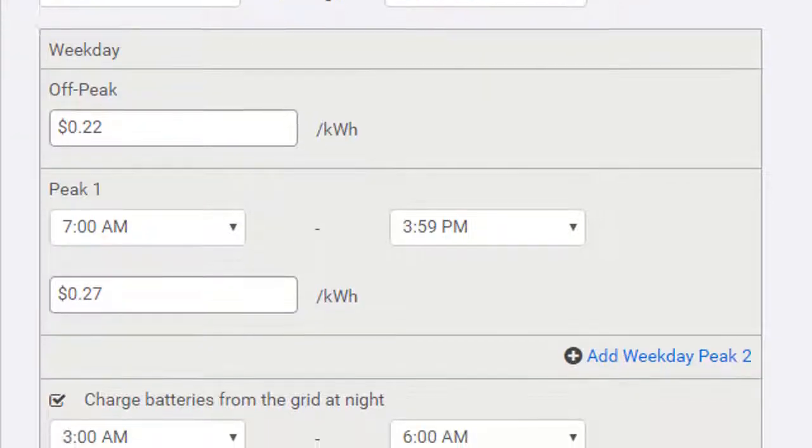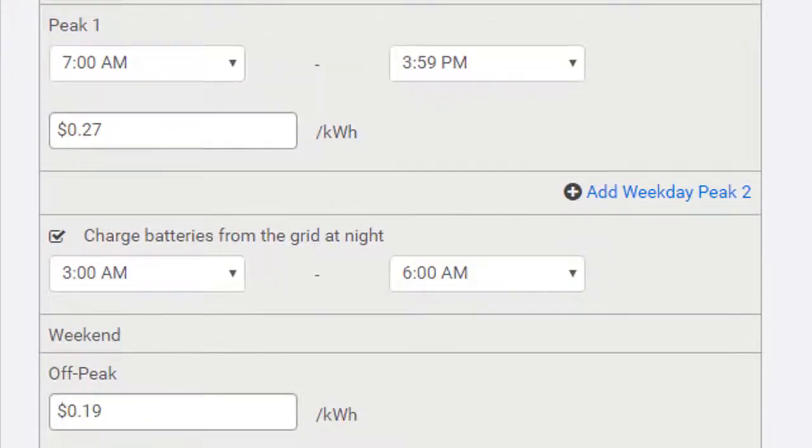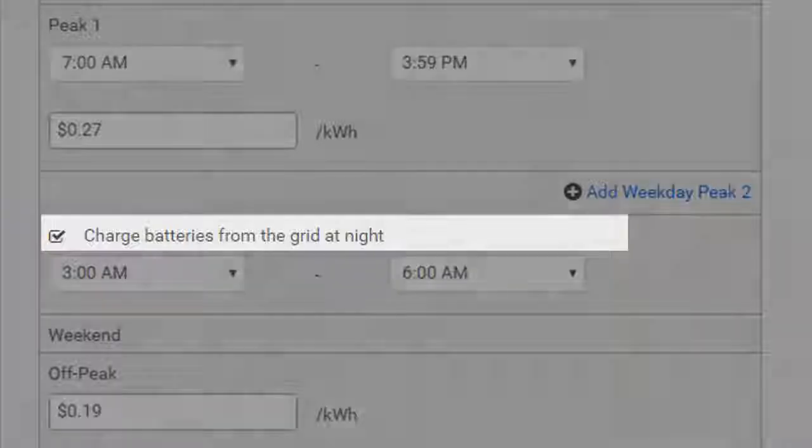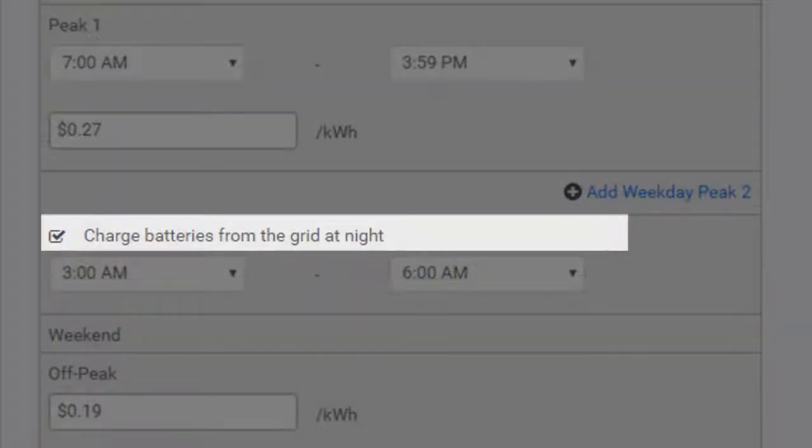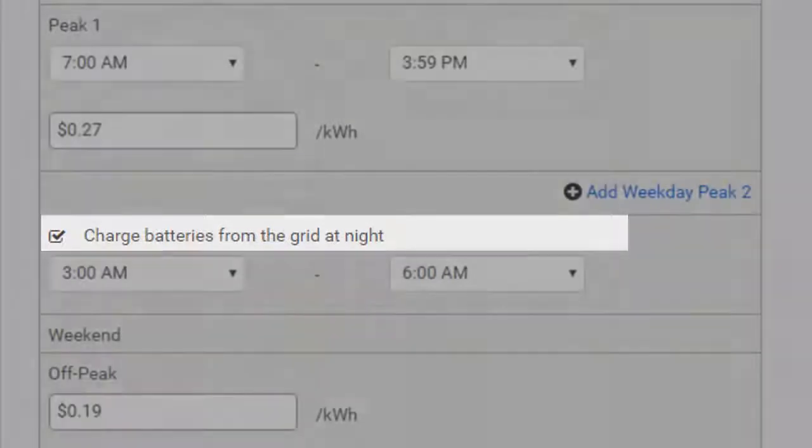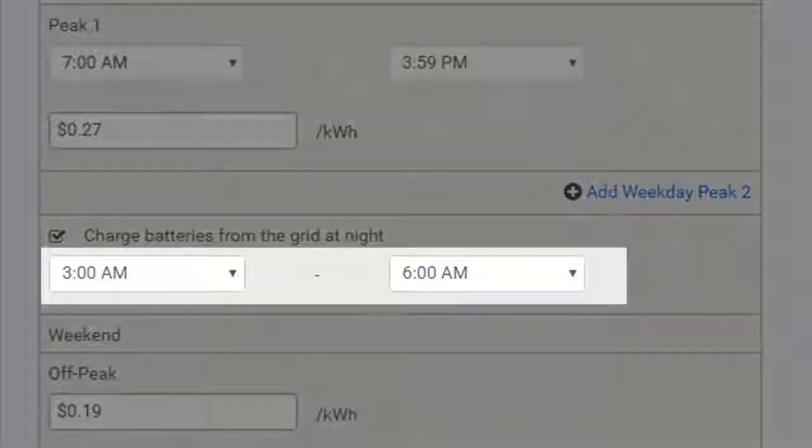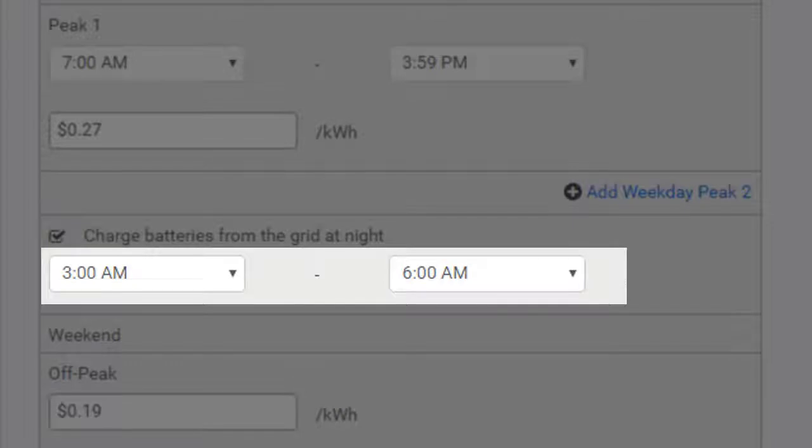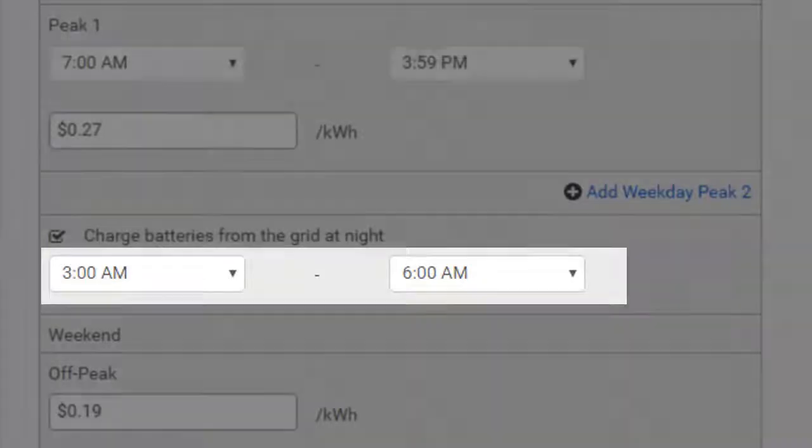Finally, for each timeframe, you have the option to charge the batteries from the grid at night in preparation for a morning peak. When you select this option, you can choose the duration for the overnight charge, a maximum of 4 hours between 2 a.m. and 6 a.m. The stored energy will be saved for the next peak period.